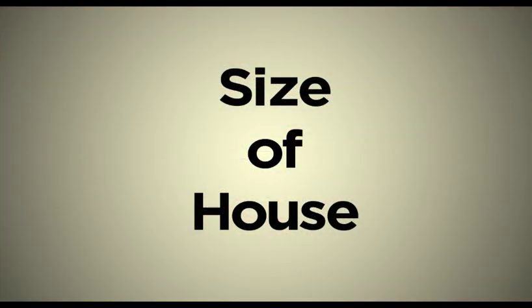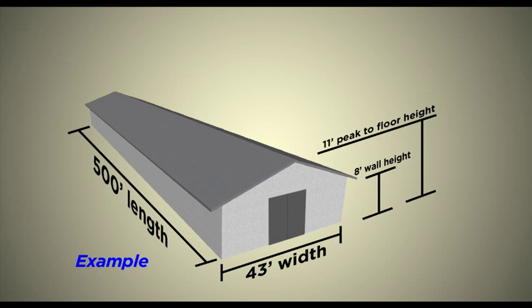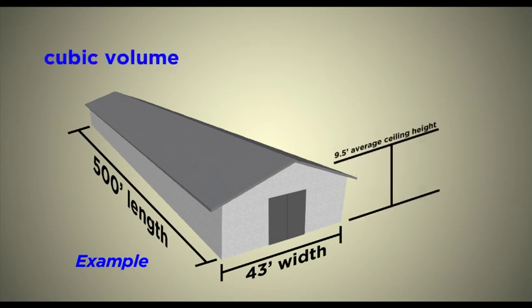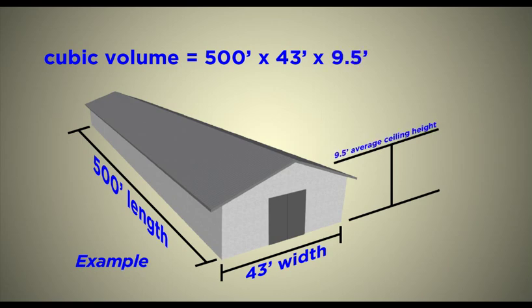To get things started, let's calculate the size of your poultry house. We need to calculate the average ceiling height. To do this, we will take the wall height — 8 feet tall — and add it to the height of the ceiling at its peak — 11 feet tall — then divide by 2. That gives us 9.5 feet as our average ceiling height. To get the cubic volume of the house, we multiply the house length (500 feet) by the house width (43 feet) by the average ceiling height (9.5 feet). The cubic volume of the house in this example is 204,250 cubic feet.